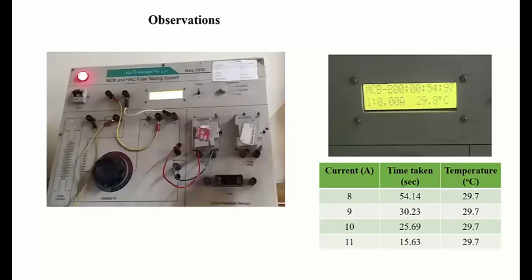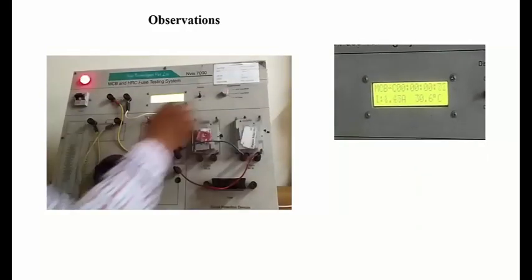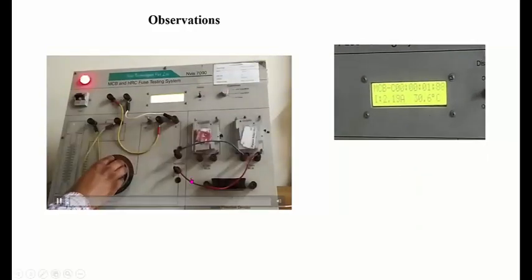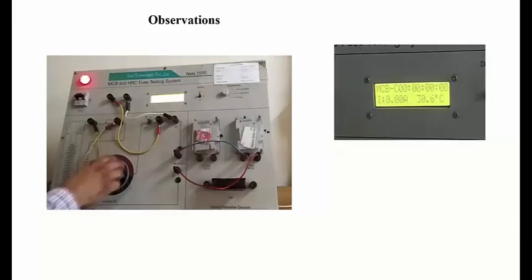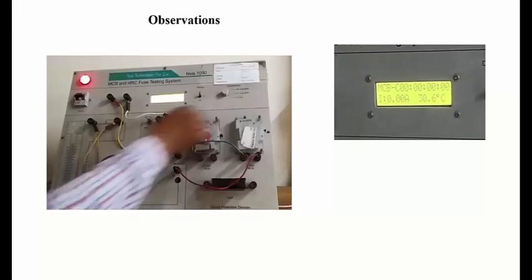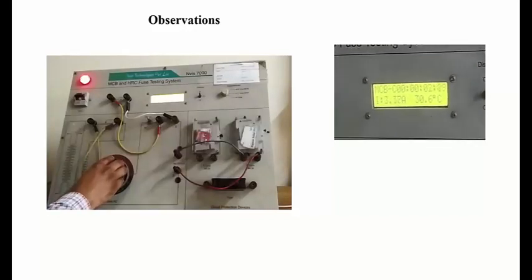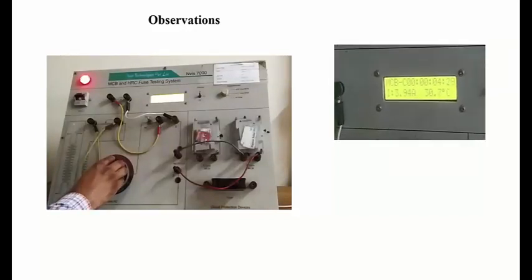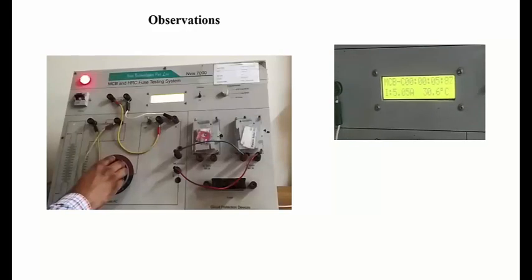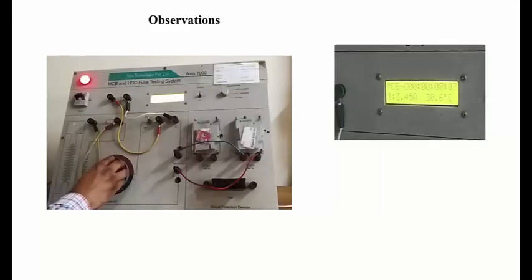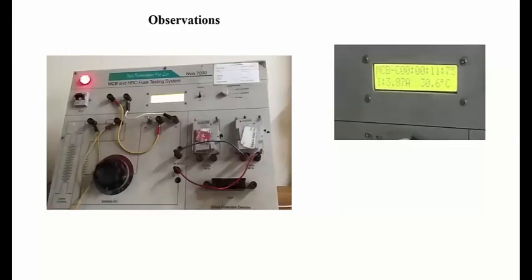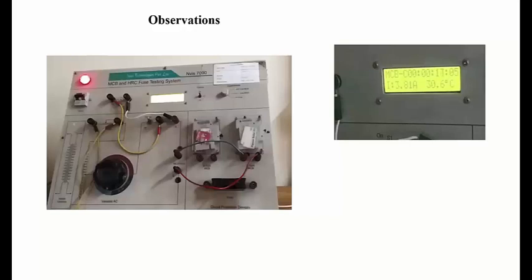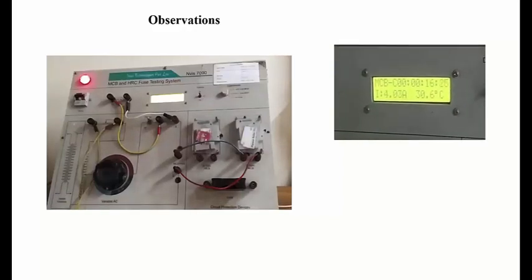In a similar way, for different values of current, we'll be obtaining different sets of readings. Now we'll be testing the type C MCB. The terminals shown in the figure are changed and connected to type C MCB. We'll maintain the current around 4 amperes for this type of MCB. The current is maintained using the rheostat.